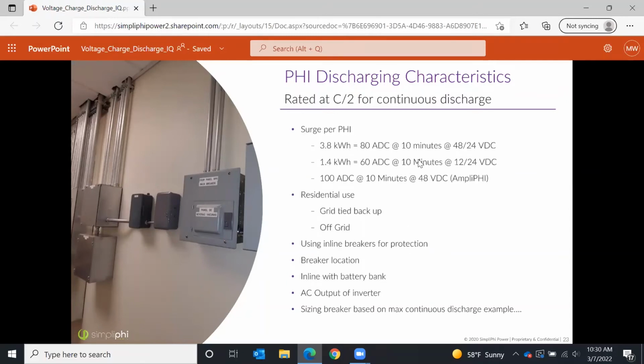However, when it comes to discharging as opposed to charging, there are surge capacities built into these batteries. Talking about 80 amps DC at 10 minutes. So for our 3.8 kilowatt hour battery, note that the 24-volt battery and the 48-volt battery have the same surge amperage. So realistically, this means if you're starting a motor or a large saw, something along those lines, a well pump, you're going to want to go with 48-volt batteries as they have a larger surge in terms of power.